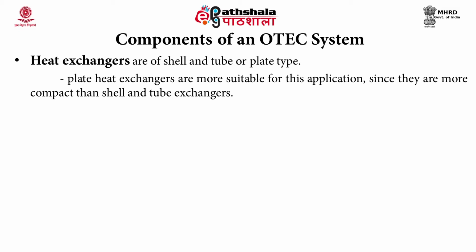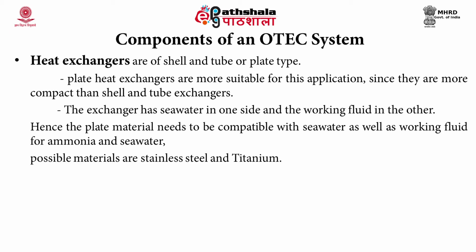Plate heat exchangers are more suitable for this application of OTEC since they are more compact than shell and tube exchangers. Here, in these heat exchangers, one side has seawater and the other has the working fluid. Hence, the plate material needs to be compatible with seawater as well as the working fluid. For ammonia and seawater, possible materials are stainless steel and titanium.